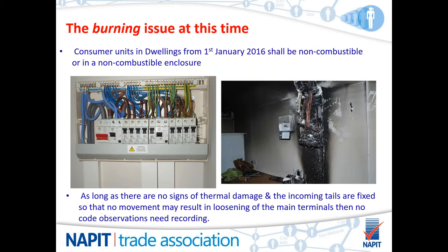Right, so the burning issue at this time is that consumer units in dwellings as of the 1st of January 2016 should be of a non-combustible material, I do apologise, or in a non-combustible enclosure. So as long as there are no signs of thermal damage and the incoming tails are fixed so as to prevent any movement which could result in loosening of the main terminals, then no code observation needs recording.